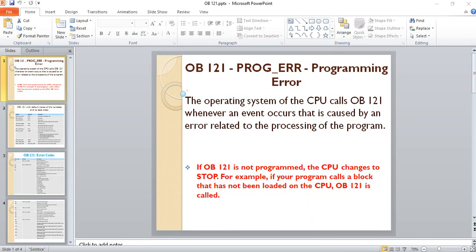Hello again. I came with another video about organization blocks used for troubleshooting. We will see OB-121 on this video. OB-121 is a programming error block. The operating system of the CPU calls OB-121 whenever an event occurs that is caused by an error related to the process of the program.